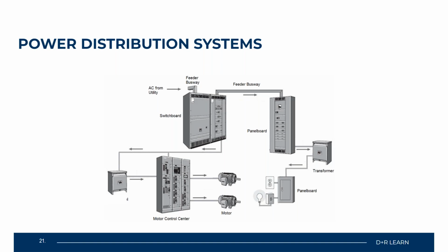Now we can tie everything in when we go through the power distribution system to see how all of these different components come together. So in the beginning, we spoke of our switchgear, which is this device right here, which is going to receive the commercial power coming in from the utility. That commercial power is going to be sent over where it's required. But before it gets there, the transformers that we spoke about are going to reduce that power coming in from the utility, because the power coming in from our utility is normally pretty high. At a large facility, you're probably going to have somewhere around 600 volts coming in. Your feeder or your switchgear is going to have that power transferred over to where it's needed, but your transformer is going to reduce that power load, so that it is exactly what we need where we need it.